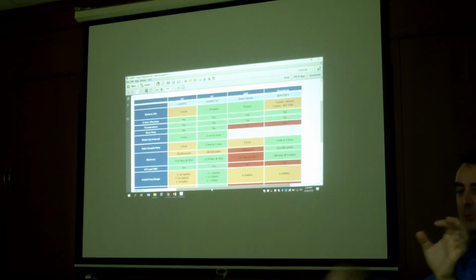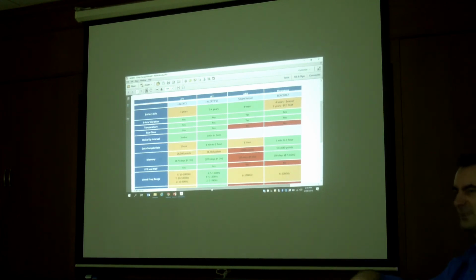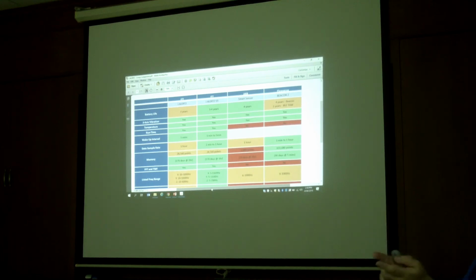I had one person in Australia, a sales engineer. We had an iAlert that we increased to 1 minute. And then he put it to sleep because it was just for troubleshooting. We used it 2 or 3 times. Turn it on, put it on this pump, get 2 days worth of data, put it to sleep. So we didn't use the battery. But then we needed to use it for something else. So he put it on another pump and we forgot that he left it at 1 minute. It died after 1 month and 4 days. But I'm happy. I said, hey, you had 1 minute. I could tell because I went to the website and I could see every single minute I had a piece of data. So we knew that the sample rate was up. But it worked very well for what it did. So the battery life is good these days.